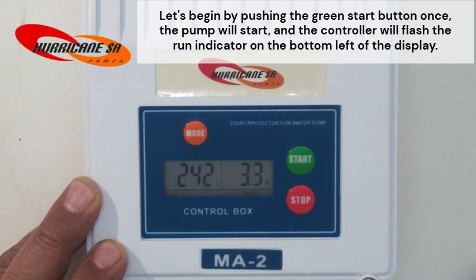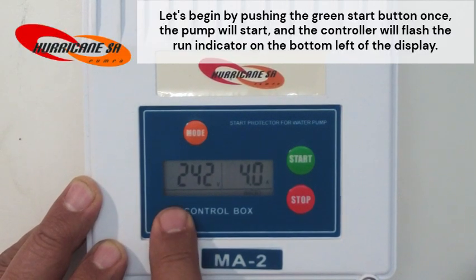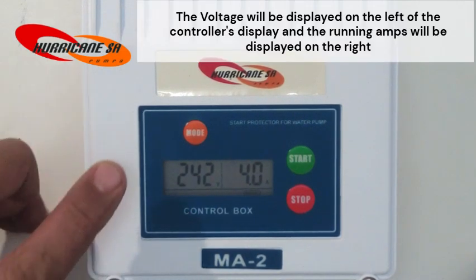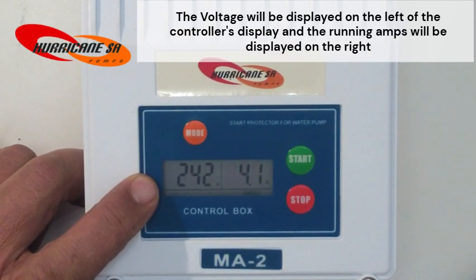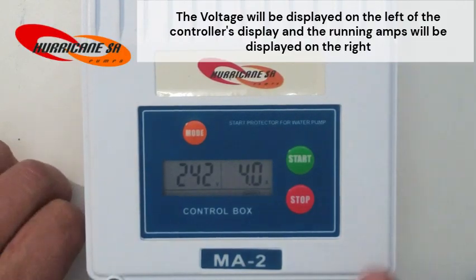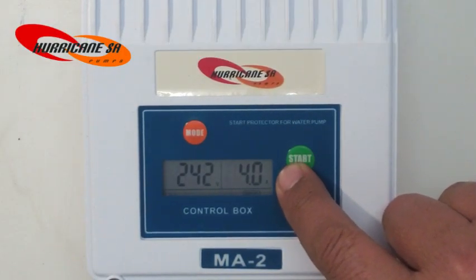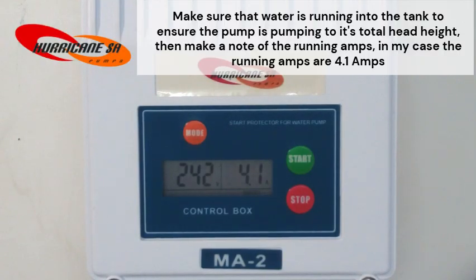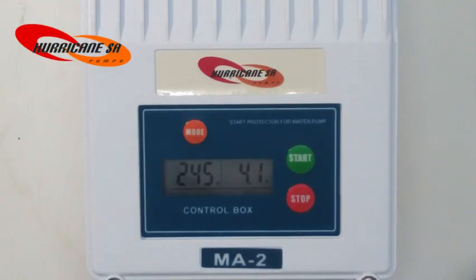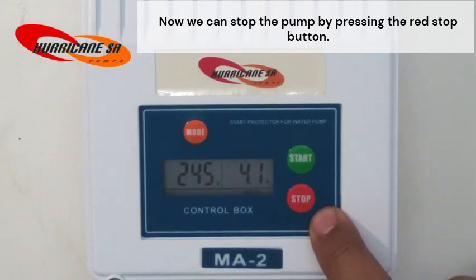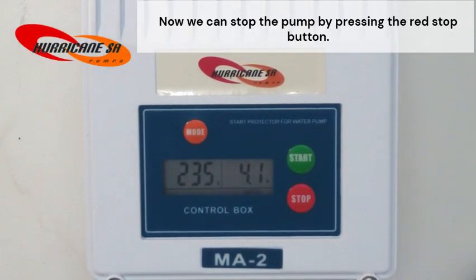The pump will start and the controller will flash the run indicator on the bottom left of the display. The voltage will be displayed on the left of the controller's display and the running amps will be displayed on the right. Make sure that water is running into the tank to ensure the pump is pumping to its total head height. Then make a note of the running amps. In my case, the running amps are 4.1 amps. Now we can stop the pump by pressing the red stop button.